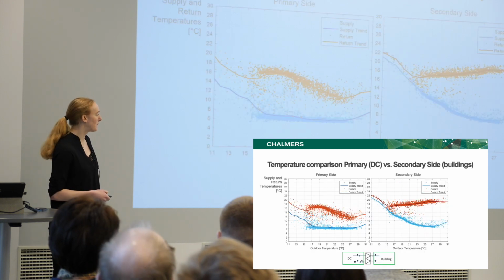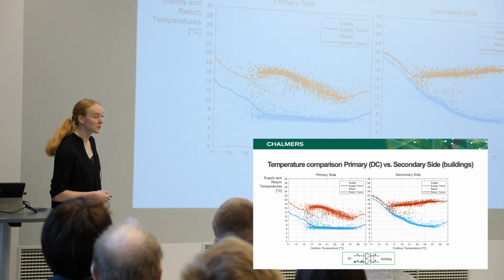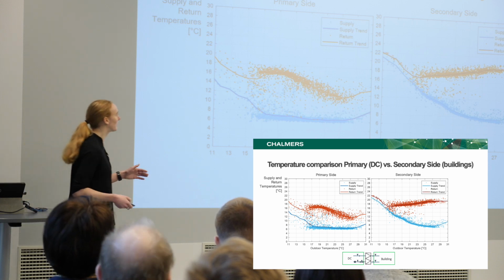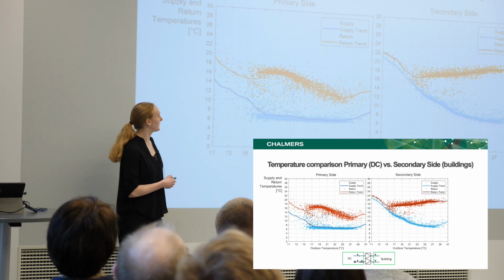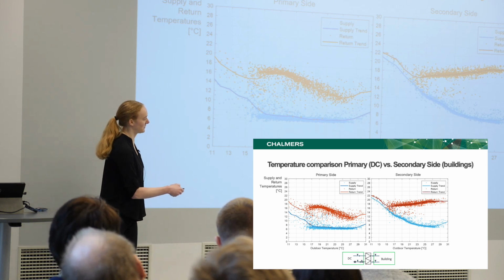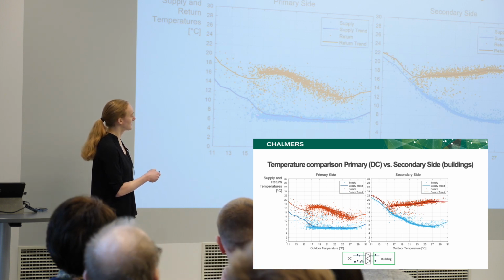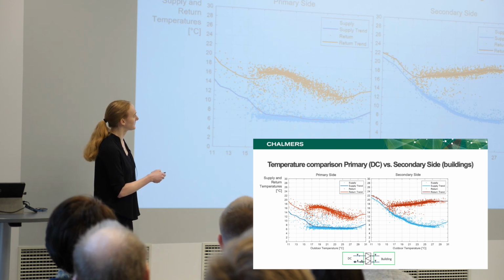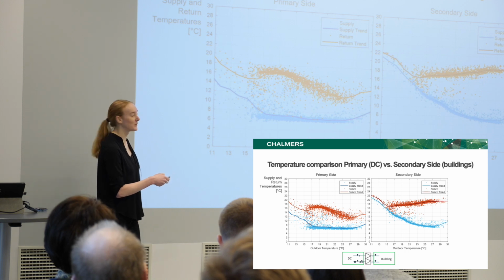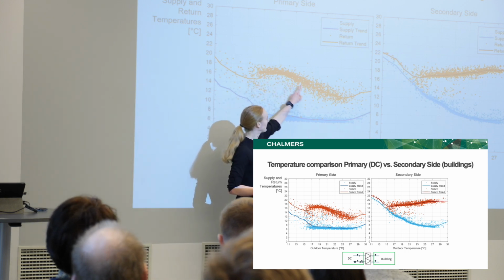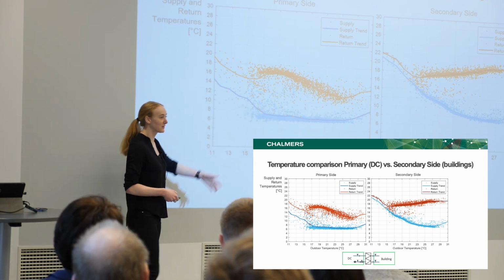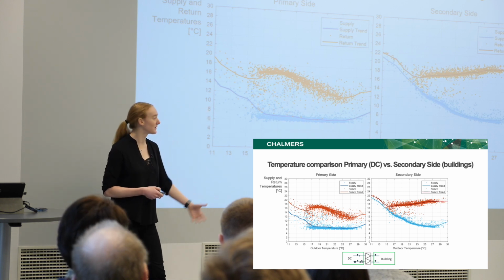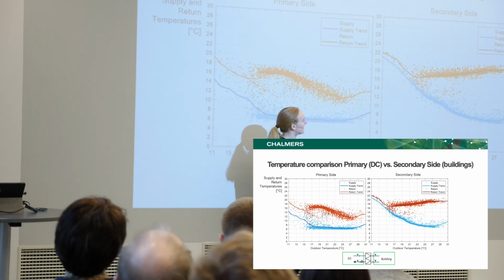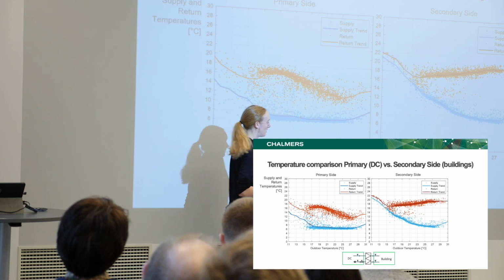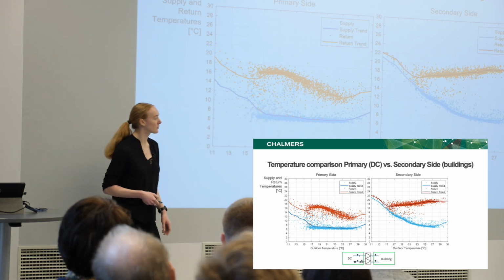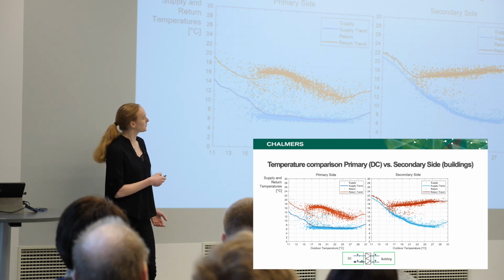If we move on to both sides of the heat exchanger, so building plus district cooling side, this is quite interesting, because if the utility provider only has data from here, we still have outdoor temperature on this axis. This is the supply temperature, around 6-7 degrees, but here is the return temperature for this substation. If you didn't have this side information available, you would think, okay, it looks good, and then when the temperature gets warmer, the return temperature drops. Probably because this customer doesn't have a good return temperature in the building. But when we have temperature from the building, we know that that's not the case. This customer has a really good return temperature on this side of the heat exchanger. So there has to be something else causing the temperature to drop like this.